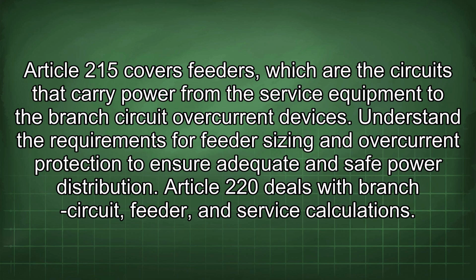Article 215 covers feeders, which are the circuits that carry power from the service equipment to the branch circuit overcurrent devices. Understand the requirements for feeder sizing and overcurrent protection to ensure adequate and safe power distribution.